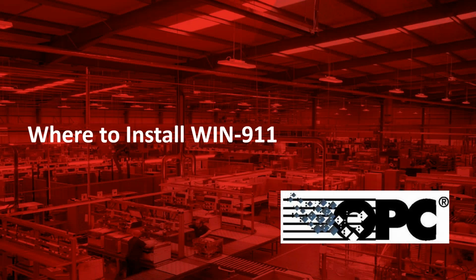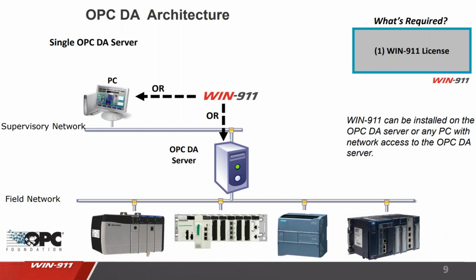So where to install WIN-911? It's pretty easy with OPC. With a lot of other SCADAs, you have to install on that actual SCADA server, or at least have the files from an installation of something like FactoryTalk or InTouch so that we can access those files. But with OPC, you can do it directly on the OPC server, install WIN-911 right there, or it can be on another machine that's remote, but on that same network, so they can talk to each other.